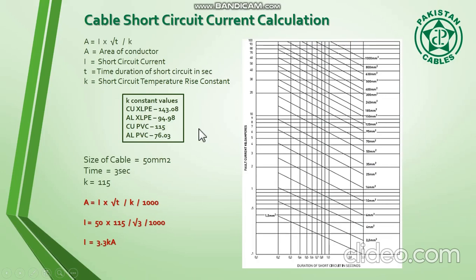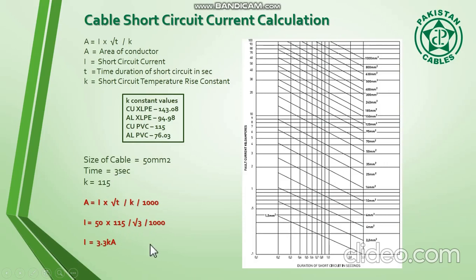Now we can calculate using the formula and verify if this is correct. We rearrange the formula and measure the area of the conductor, which is 50mm², multiplied by 115 — 115 is the constant K value for copper PVC. We divide by root T, where T is 3 seconds, so we have root 3, divided by 1000 to convert units.